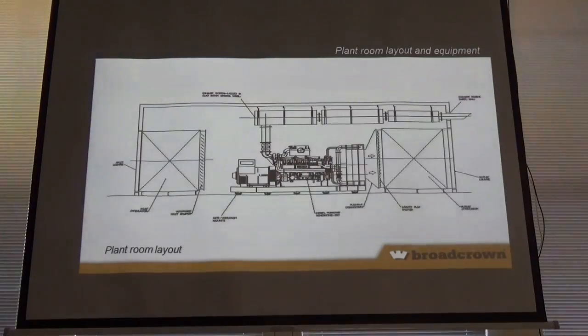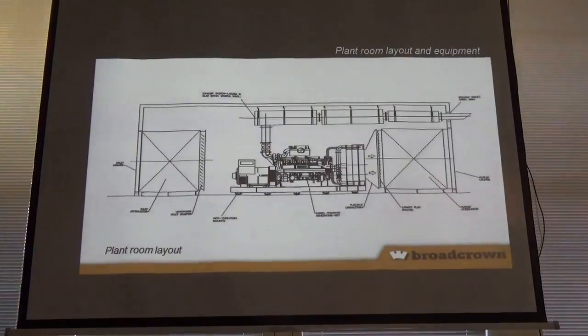The more onerous the attenuation, say 75 dBA at 1 and then more onerous 65 dBA at 1, the implication difference with those two, ignoring cost, is length, because the ear picks up most of the low frequency sound. Unfortunately, often the way of absorbing or attenuating the low frequency sound element is a function of length more than anything. You do get different air gaps between the vertical splitter blocks for each one of these attenuators, because if you looked end on of that attenuator, ignoring the louvers, all it is a series of blocks and air gaps between them, literally like a sandwich.